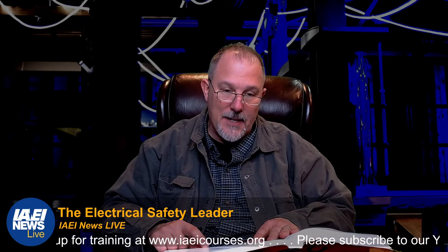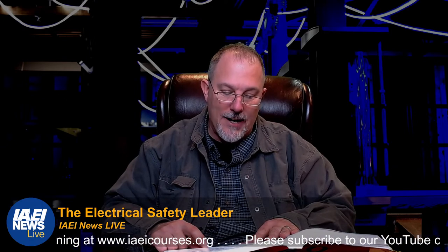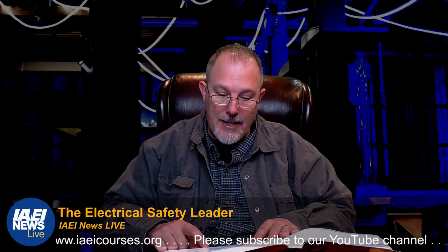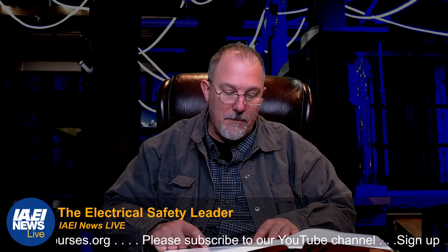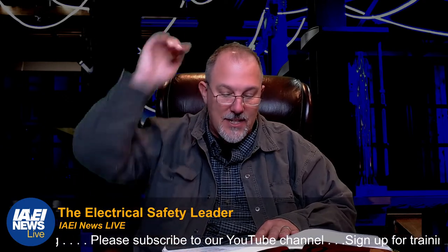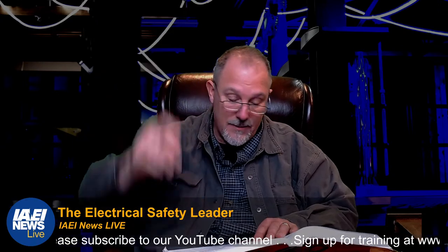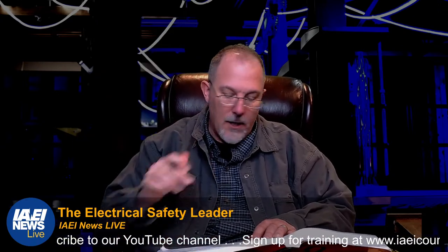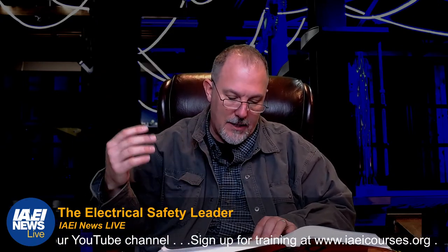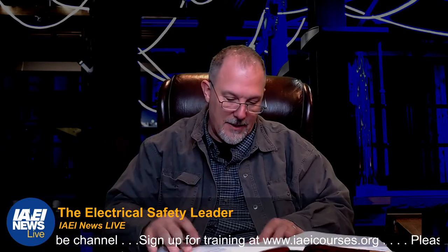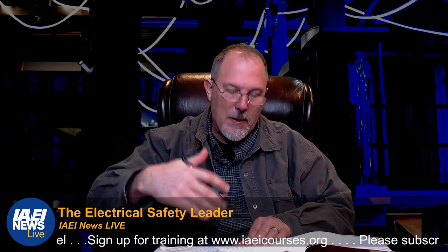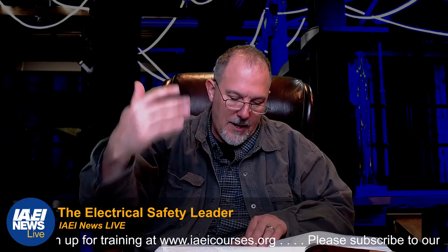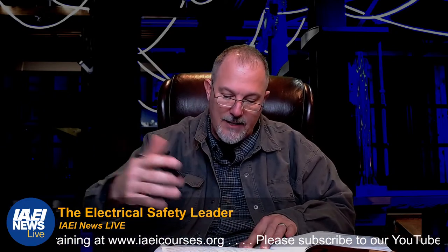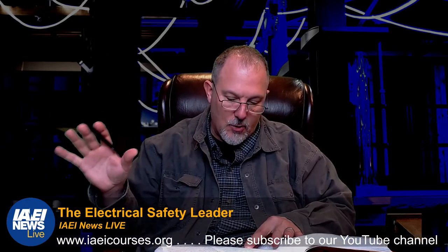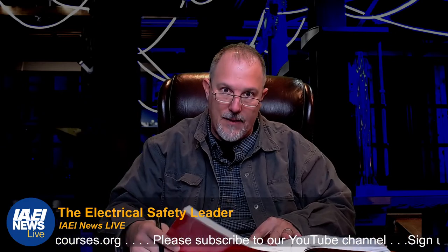Now they have an exception. Where the live parts are not accessible during routine energy storage system maintenance, a maximum voltage of 600 volts DC is permitted. Interesting. All right, so space is about workspace. They talk about dwelling units and they have a directory identifying all your energy storage systems at the location.